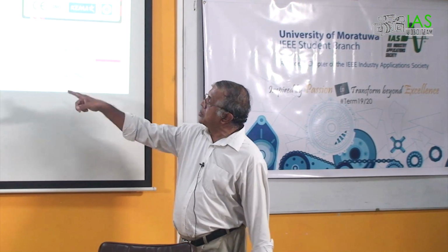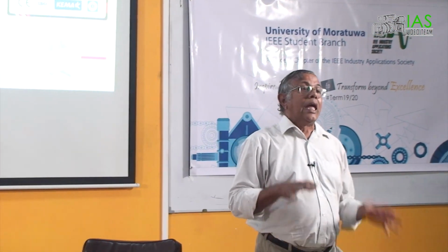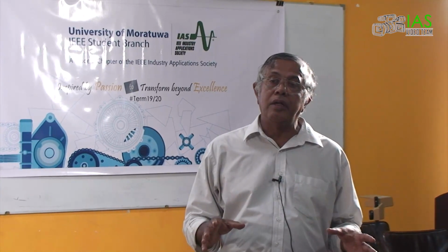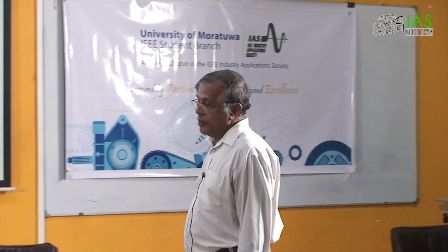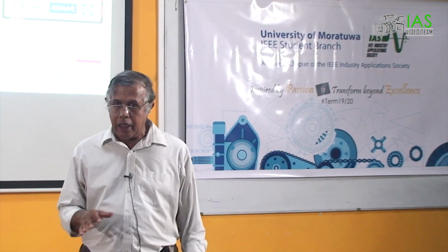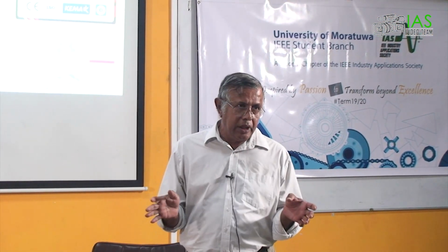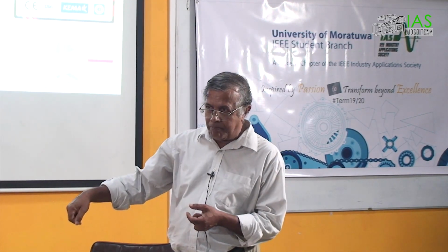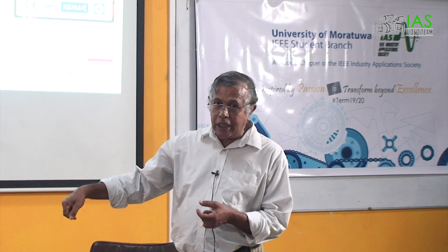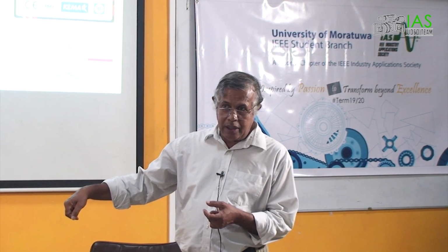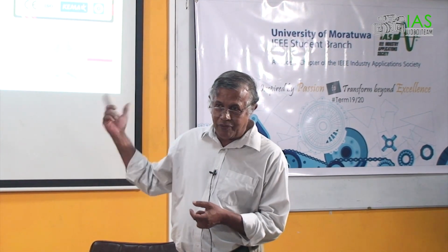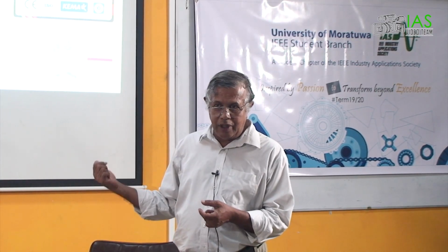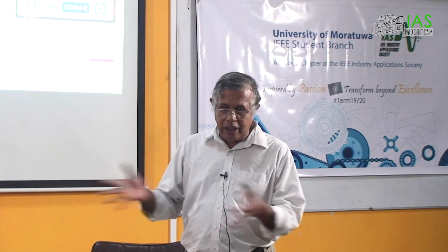That is called the ingress protection level, the IP level. The IP level goes up to totally dust protected and totally water protected. So a submersible pump would have IP68. The first digit 6 means dust protected, and the second digit 8 means water protected. Water can't go into that.